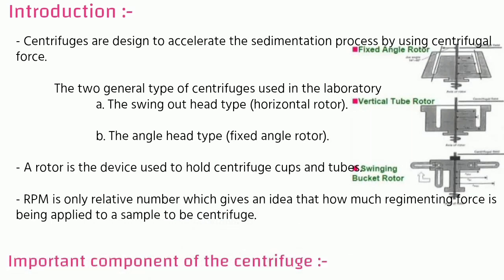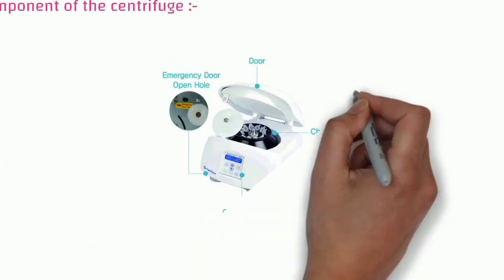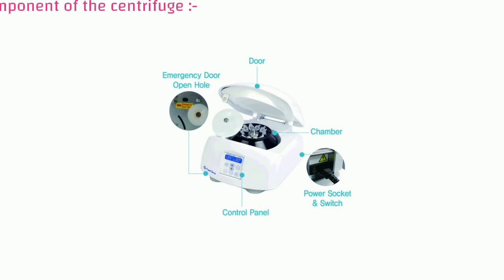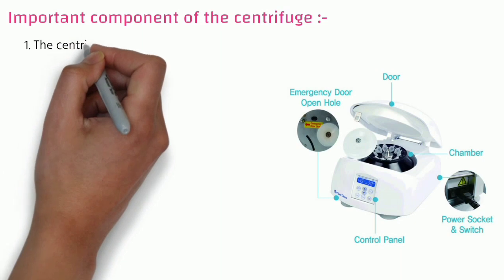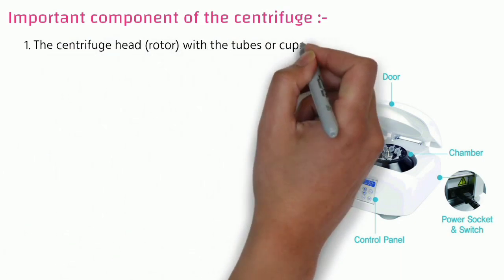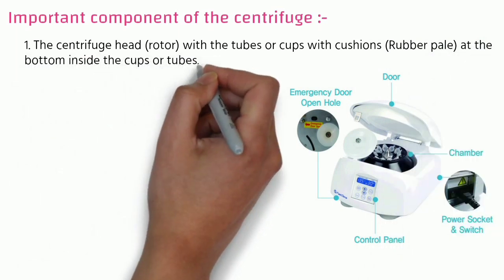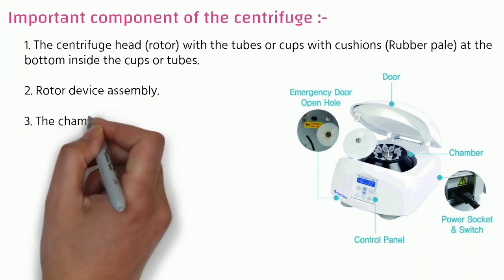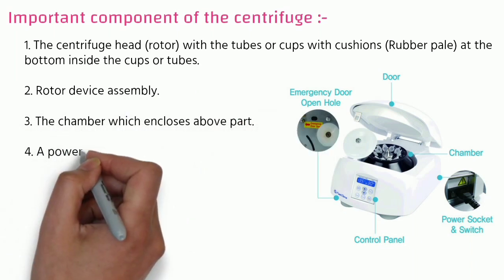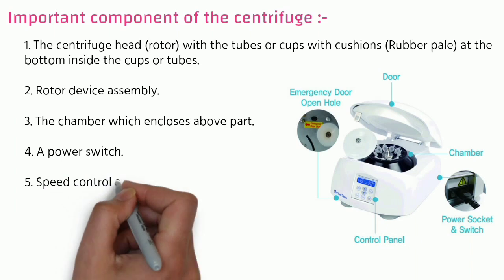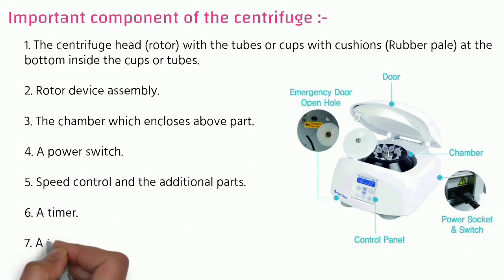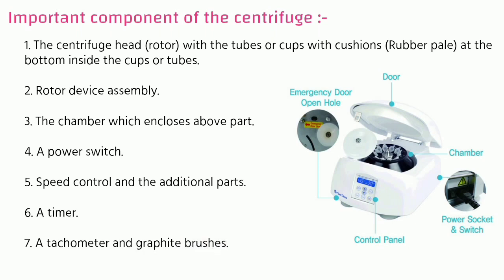The important components of a centrifuge include: the centrifuge head, meaning the rotor with tubes or cups with cushions — where a cushion is the rubber pad at the bottom inside the cup or tube — then the rotor device assembly, the chamber which encloses the rotor part, a power switch, speed control and additional parts such as a timer, a tachometer, and graphite brushes.